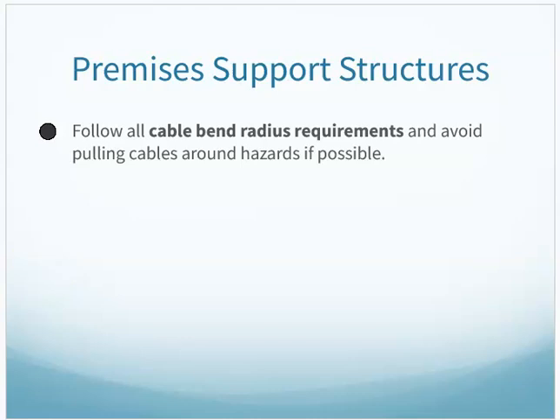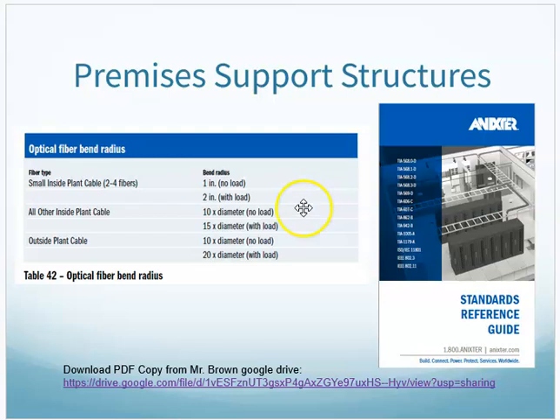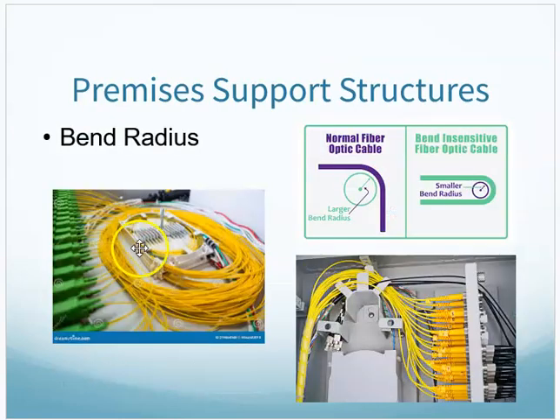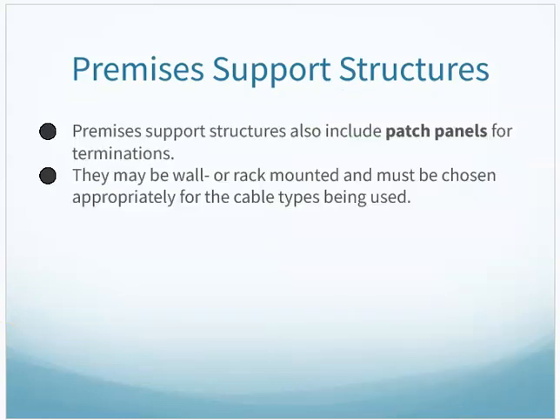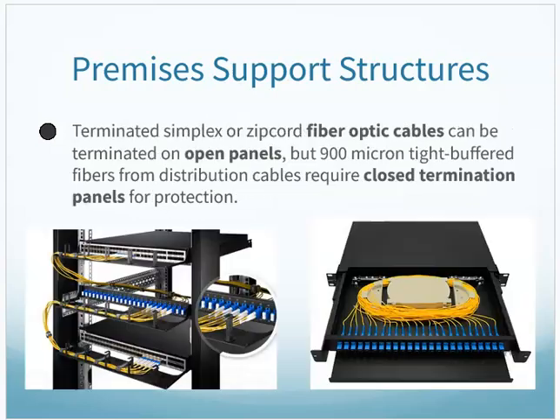We need to worry about our cable bend radius as we're installing too. If we're looking at fiber optic, we have the inside plant, we're talking 10 times or 15 times the diameter of the cable for bend radius. And I'm looking at this kind of thing here, carefully coiling and servicing and making sure I don't have any sharp bends in my cabling. I need to make sure I have patch panels in place or the appropriate splice hardware in place for my terminations.